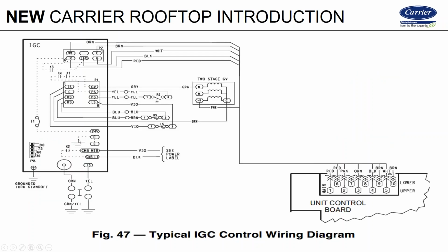Now, this is kind of how it's wired in. There are two IGC boards. There's one for 460 volt models and there's one for 208, 230 volt models. So make sure you get the right ones in there. You can see it monitors the limits, the rollouts. There's your pressure switch now, and you no longer have a Hall effect sensor 1, 2, 3 connector. That's gone. So basically it controls your gas valve and monitors your limits and controls your fan in the auto modes. And of course it looks at your flame rectification to prove ignition.